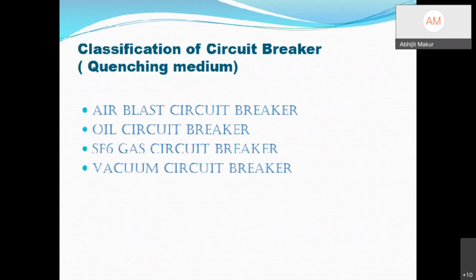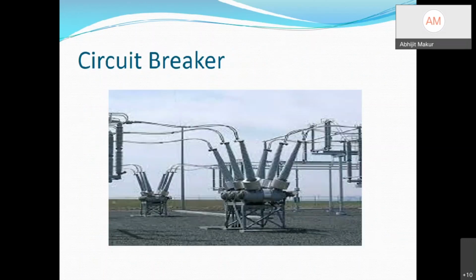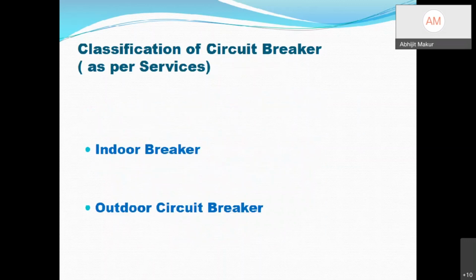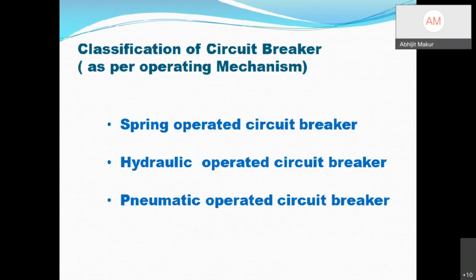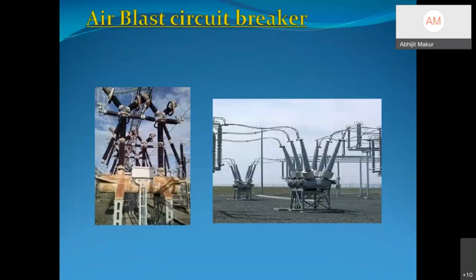The circuit breakers, basically, if we divide them by quenching medium, there are 4 types: air blast, oil circuit breaker, SF6, and vacuum. But in terms of service, you can use either indoor switchgear or outdoor switchgear. You can also classify them as per the operating mechanisms: either a spring operated circuit breaker, hydraulic, pneumatic, and sometimes a combination of two. Hydraulic and spring operated, or pneumatic and spring, is what is commercial now in service. The air blast circuit breaker is the one that has often been discussed by earlier panels. I don't want to go into it.